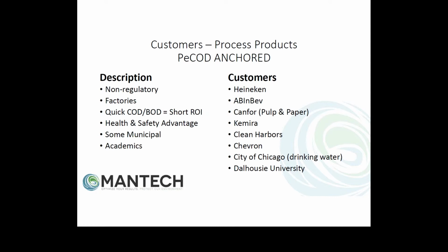Our mission is about fast and green. For example, getting our fast 10-minute COD BOD analyzer with a green method is about internal operation, and the ROI is very clear. It's about the 10-minute result - faster than the 3-hour dichromate method, and certainly faster than a 5-day BOD.